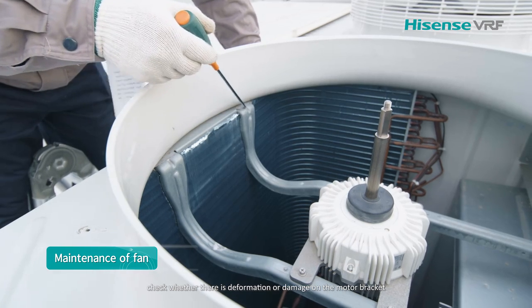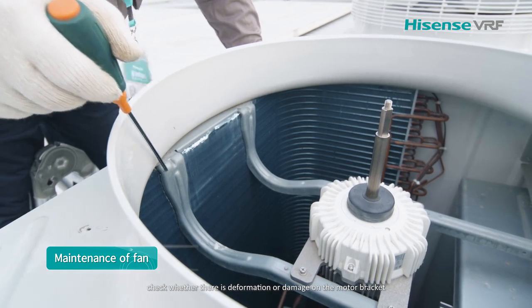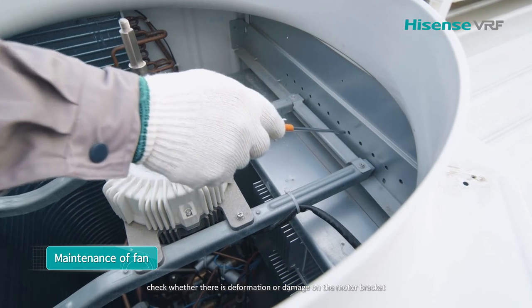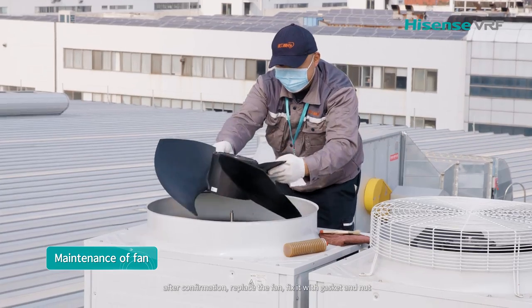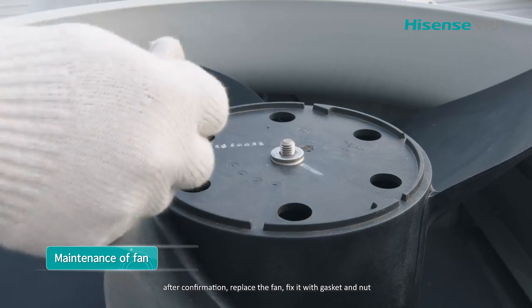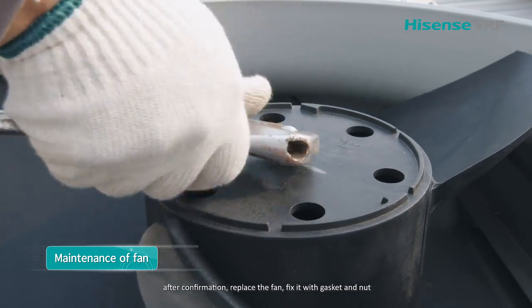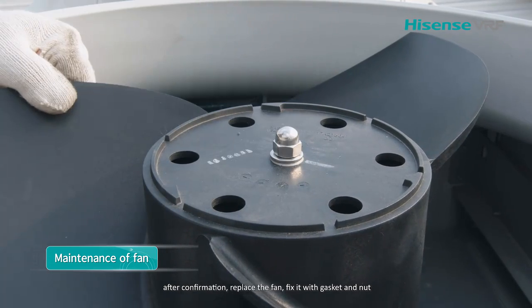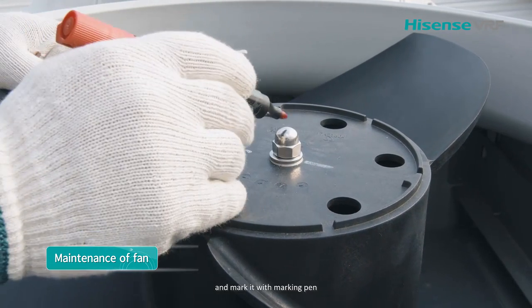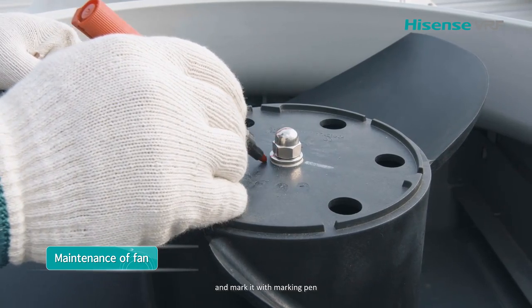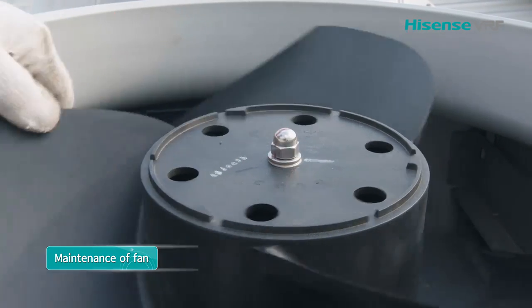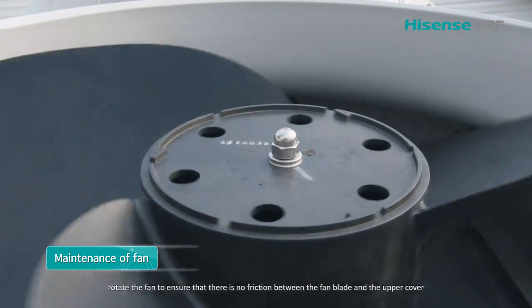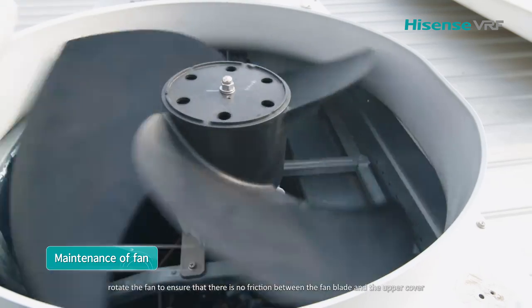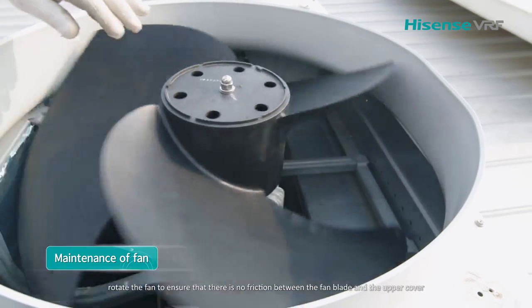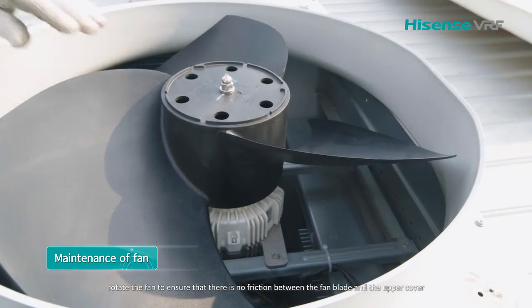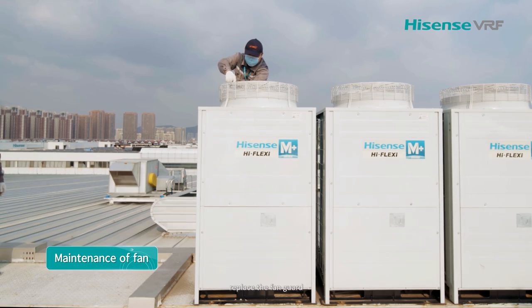Check whether there is deformation or damage on the motor bracket. After confirmation, replace the fan. Fix it with gasket and nut, and mark it with marking pen. Rotate the fan to ensure that there is no friction between the fan blade and the upper cover. Replace the fan guard.